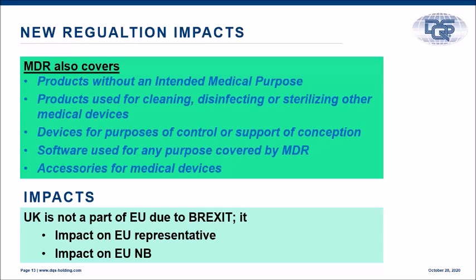Software used for any purpose is covered under MDR. So for software, there is a specific focus given in the regulation, including software alone as a medical device, and software controlling medical devices, and how it needs to be classified. So all those things have been given. Of course, there is this Brexit impact which is there, so I'm not going to go into detail about that.